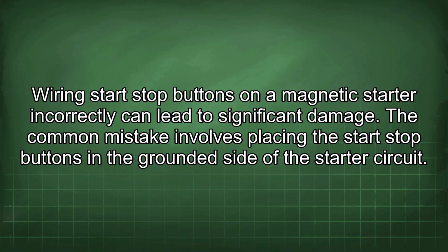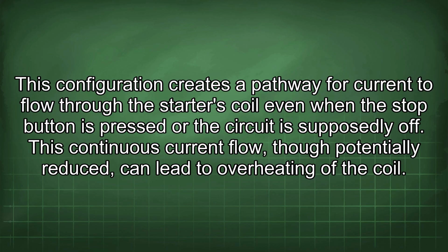Wiring start-stop buttons on a magnetic starter incorrectly can lead to significant damage. The common mistake involves placing the start-stop buttons in the grounded side of the starter circuit. This configuration creates a pathway for current to flow through the starter's coil even when the stop button is pressed or the circuit is supposedly off.